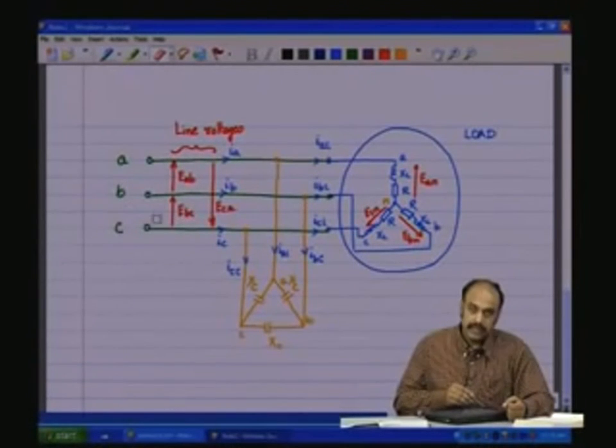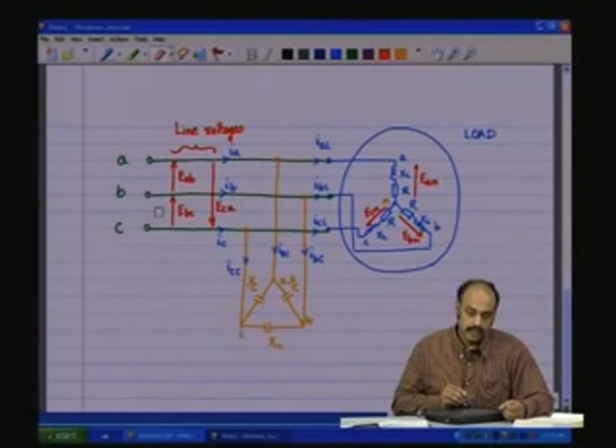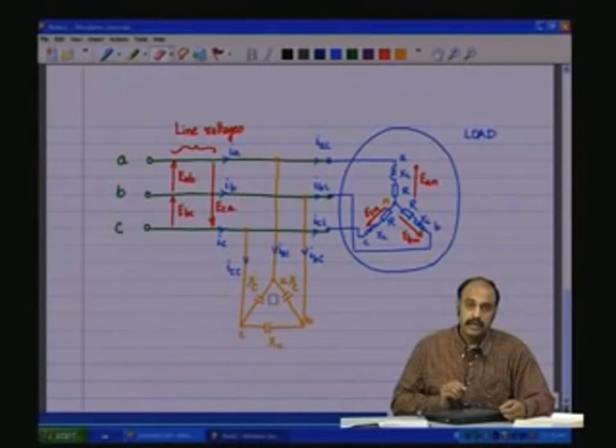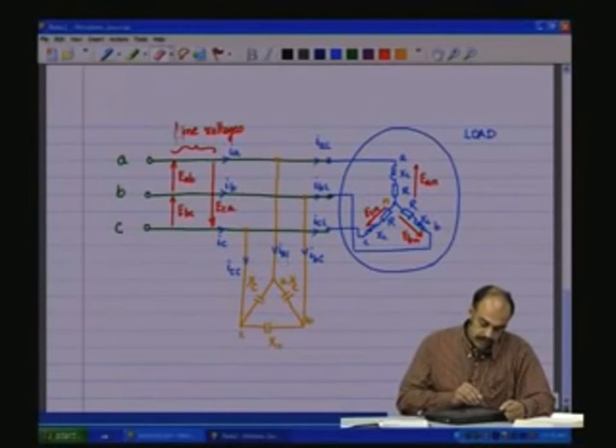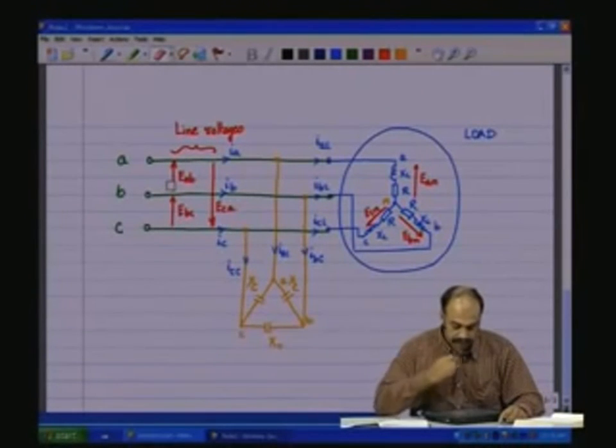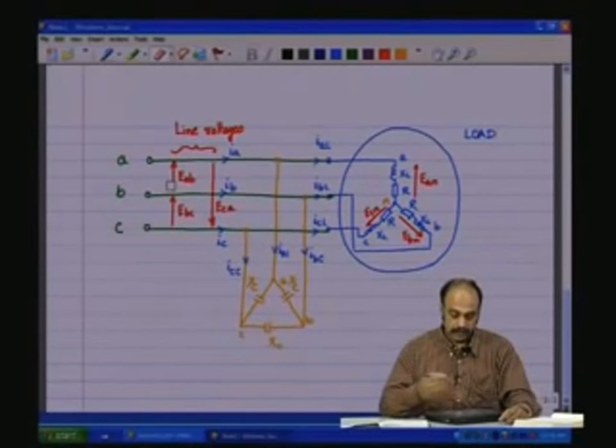Therefore, to compensate for the reactive component, so that it can be delivered to this buffer capacitance and then taken again as and when required, the capacitive reactive network as shown here is generally used, so that the power factor as seen from the line side or the source side is improved. That will become evident once you look at the phasor diagram.